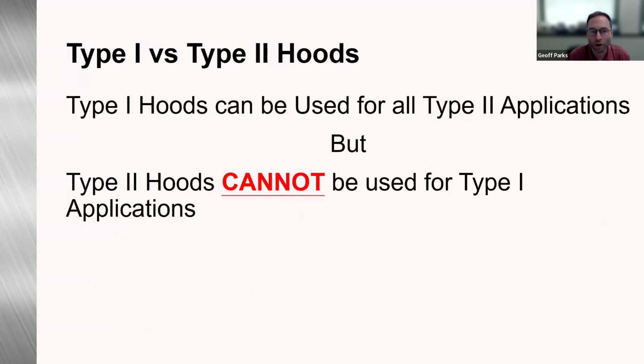So type 1 hoods can be used for all type 2 applications, but under no circumstance can a type 2 hood be used for any type 1 applications. So you can substitute a type 1 hood for all type 2, but it's not vice versa. You cannot use a type 2 where a type 1 application is required.